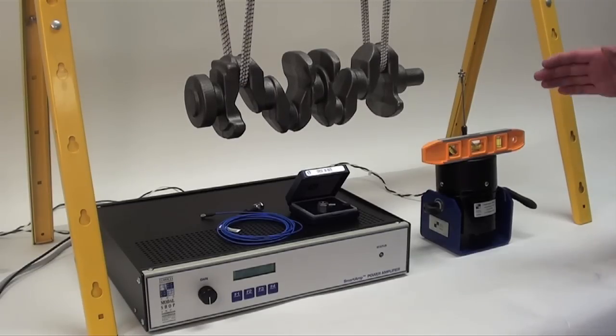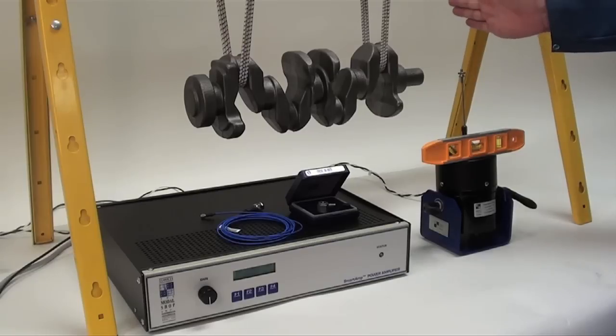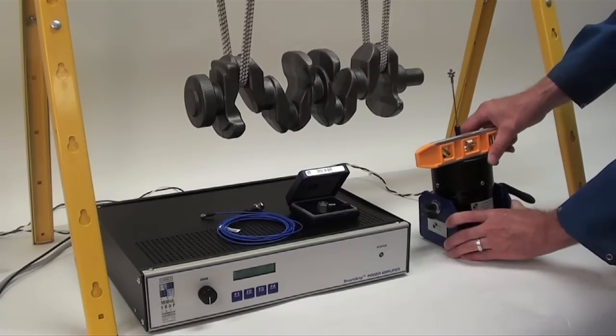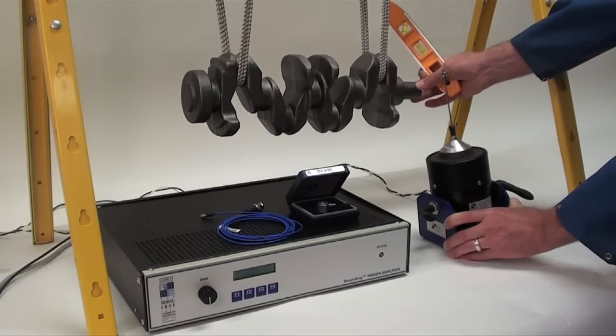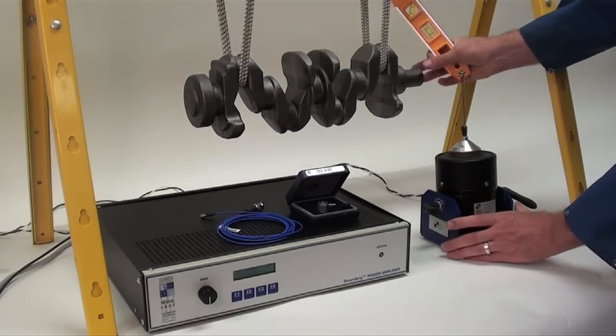So that means that when we excite the test article, we're more likely to get the orthogonal directions that we're interested in. It will be exciting along predetermined axis, as opposed to having the shaker canted at some angle and the crankshaft at a different angle. So we'll get everything leveled up.